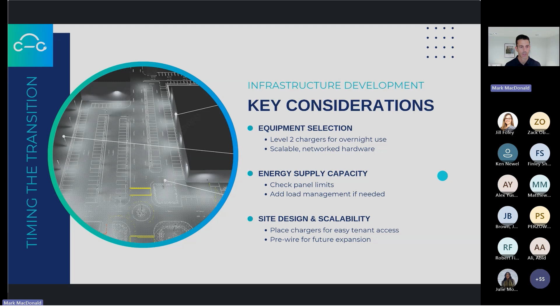Charger specifications: we only really sell two versions of Level 2, 48 or 80 amps, so engineers can select the amperage that makes sense for that panel. We still see a lot of EV-ready requirements at 32 or 40 amps on the EVSE side, so you can tune these chargers down mechanically, which is also recognized by code, without having to size the branch circuit based on total capacity.